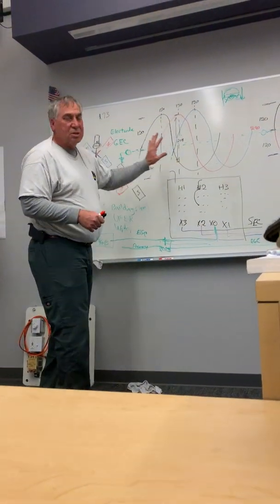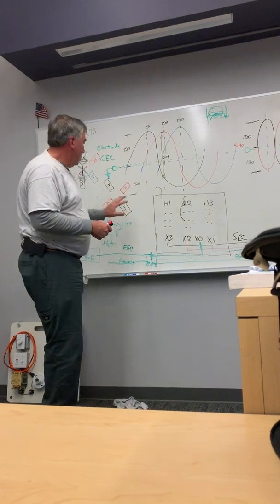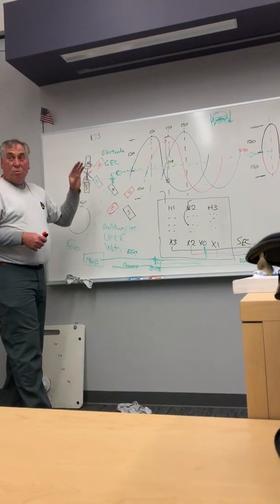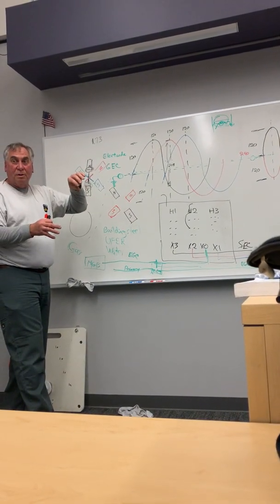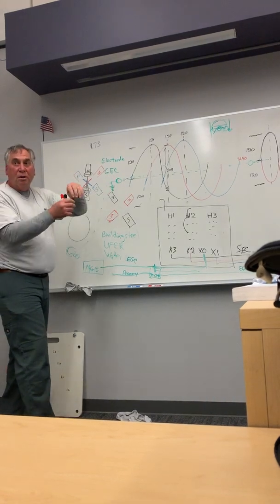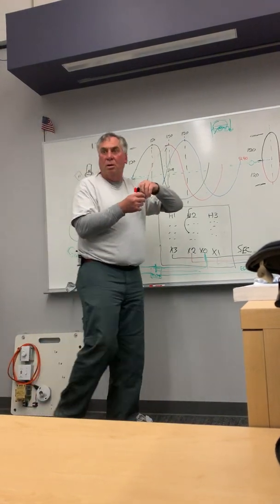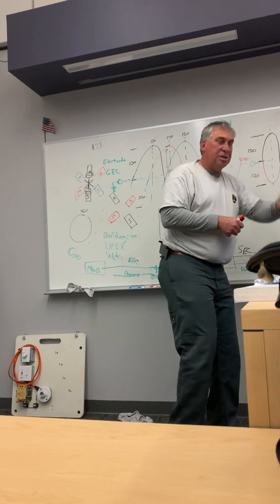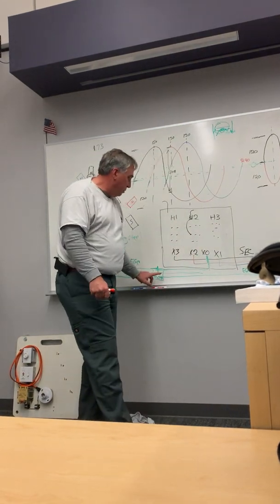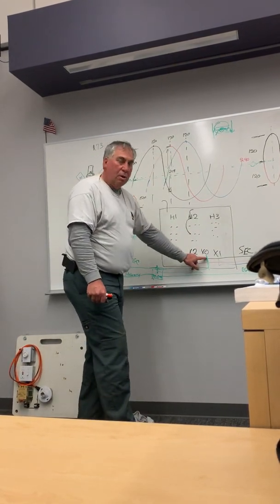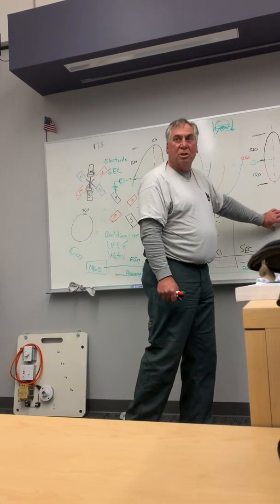The rest of all the sub-panels on the job, the ground and the neutral are separate, but at this service, the ground and the neutral are the same bar, only in one place. It's either at this transformer, or in the first service entrance conductor.